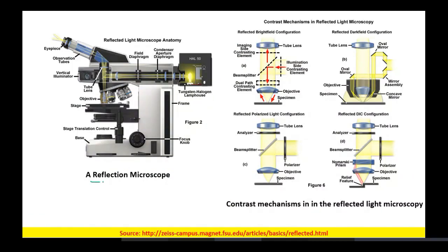In the reflection microscope, the illumination system and visualization system are on the same side of the sample. Light goes through the condenser aperture, diaphragm, field diaphragm, and condenser, then through the objective onto the sample. The reflected light returns through the objective into the eyepiece system. Reflected light microscopes have similar contrast mechanisms to the upright microscope.